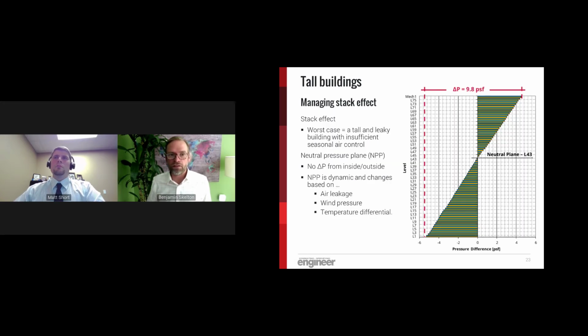You can't control stack effect. You can't tell it what it's going to do, but you can try to manage your building as best you can. And just a very brief overview of a stack effect case. You know, the neutral plane of your building. This is where you switch from the bottom part of the building being negative to the top part of the building being positive, or vice versa, depending on temperature differences. That neutral plane changes constantly depending on temperatures outdoors and the wind speeds. And so you need to have your building set up in a way to monitor certain metrics at certain levels of the building to understand what is happening and to be able to adjust to that.